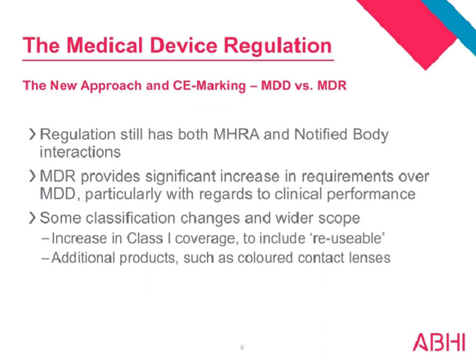The Medical Device Regulation has a significant increase in technical requirements, particularly as it relates to clinical performance, and the use of things like substantial equivalence or equivalence claims within your demonstration of that clinical performance. In addition, there are a number of classification changes where the new regulation is up-classifying some products, particularly those which are currently Class 1 products and self-declared, and now becoming reusable products.